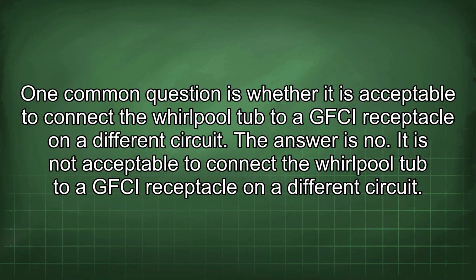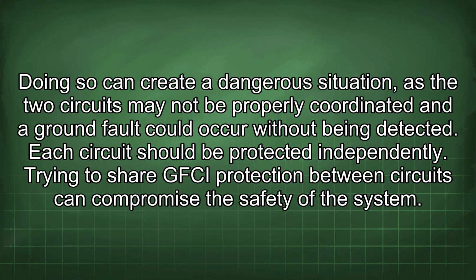One common question is whether it is acceptable to connect the Whirlpool tub to a GFCI receptacle on a different circuit. The answer is no. It is not acceptable to connect the Whirlpool tub to a GFCI receptacle on a different circuit. Doing so can create a dangerous situation, as the two circuits may not be properly coordinated and a ground fault could occur without being detected. Each circuit should be protected independently. Trying to share GFCI protection between circuits can compromise the safety of the system.